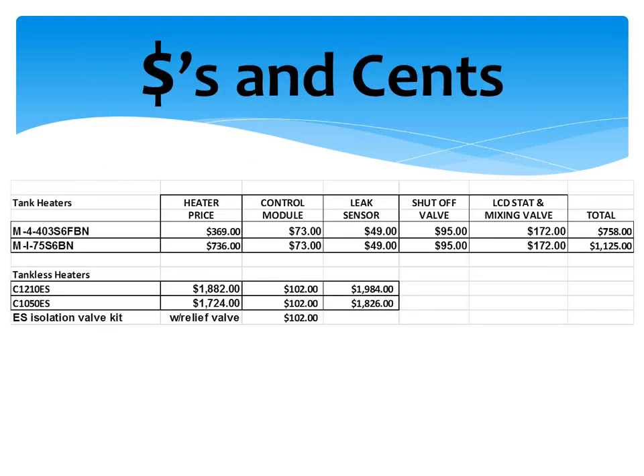A tank heater just becomes less efficient over time because scale piles up in the bottom unless you do something about it. With tankless heaters, you go in there with white vinegar, a 5-gallon bucket, a garden hose, and the isolation kit, and you flush it through until it's cleaned out. So yes, if you figure the $758 total expense for the 40-gallon water heater on the slide, 6, 7, 8 years from now, if you maintain it and transfer the accessories to another heater that will probably be $400, you could replace a tank water heater probably 3 times easily for the cost of the tankless heater.